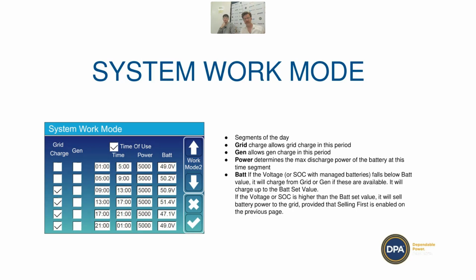Then between 6 and 8, depending on the size of your battery bank, you might set it down to like 40% or so, because you're going to need the rest of that capacity to get you through to tomorrow morning before the sun starts charging your batteries again. So you're just going to export that battery power between 6 and 8 when you've got that nice high feed-in tariff. Then after 8 o'clock, you're going to put it back to no grid charge so it doesn't charge the batteries back up from the grid. I realize it's quite confusing, but it's designed for taking advantage of these types of scheduled feed-in tariffs and export tariffs.